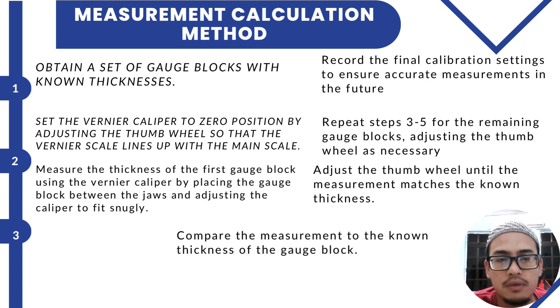Number 4 is compare the measurement to the known thickness of the gauge block. Number 5 is adjust the thumb wheel until it matches the known thickness. Number 6 is repeat steps 3 to 5 for the remaining gauge blocks and adjust the thumb wheel as necessary. And the last is record the final calibration setting to ensure accurate measurement in the future.